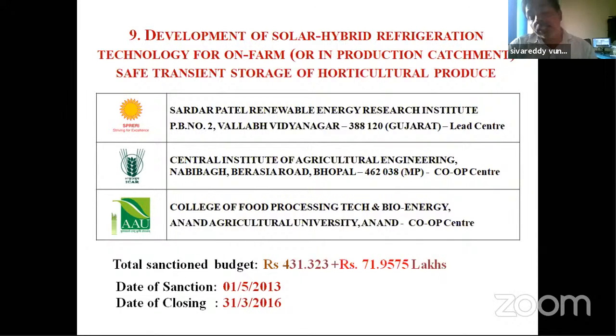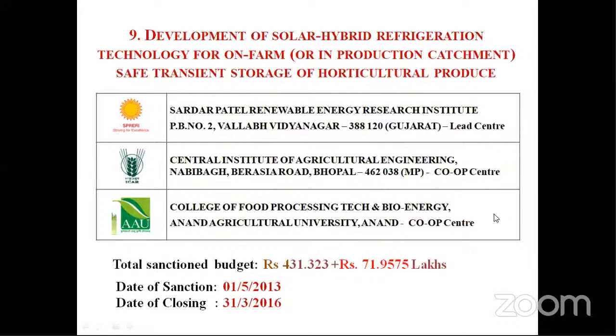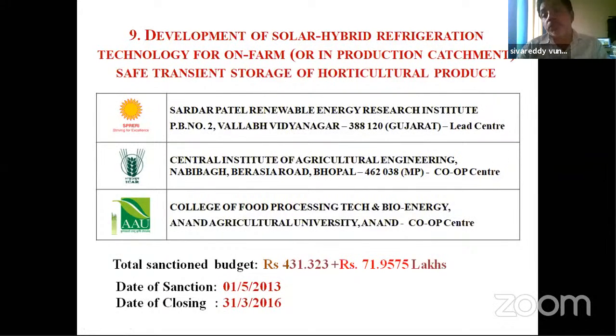Third, cold storage temperatures, according to ASHRAE norms, are defined not based on product quality but based on cooling load. Whatever temperature gives the least cooling load, ASHRAE will suggest that. For example, for tomato, 7 degrees gives effective, less cooling load, so we store at 7 degrees. But once it comes to the market, temperature is 40 degrees. Going from 7 to 40 degrees means it faces thermal shock. So due to this double transportation and thermal shock, 30% of the agriculture produce is lost.